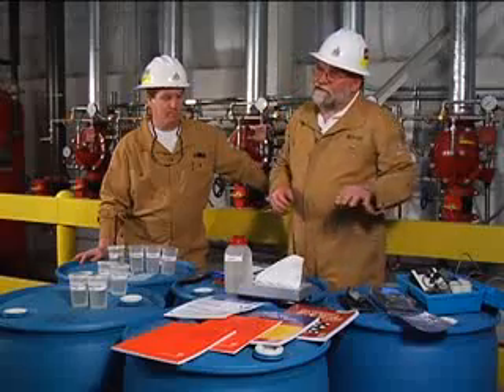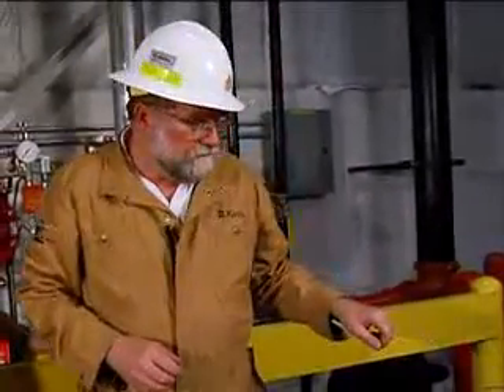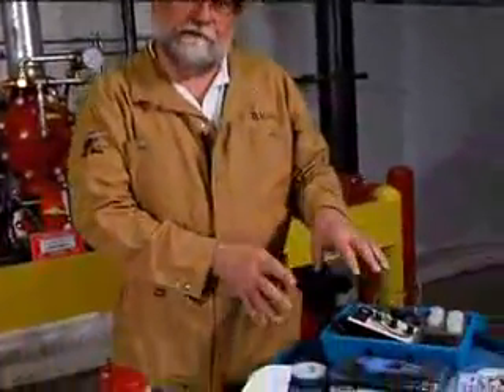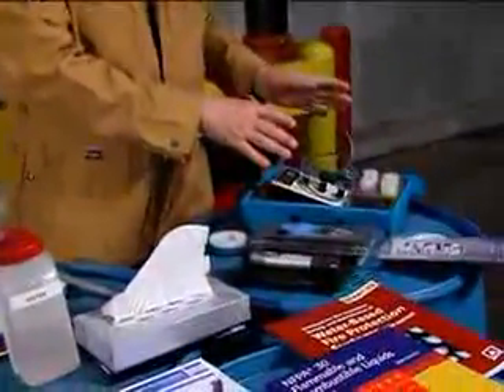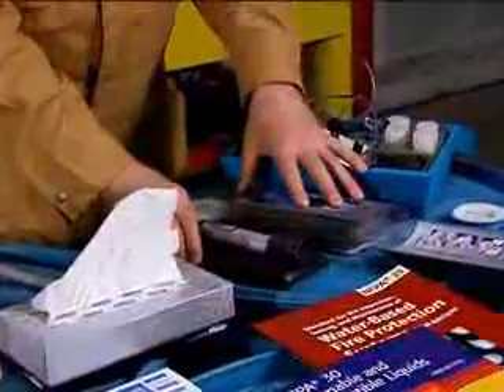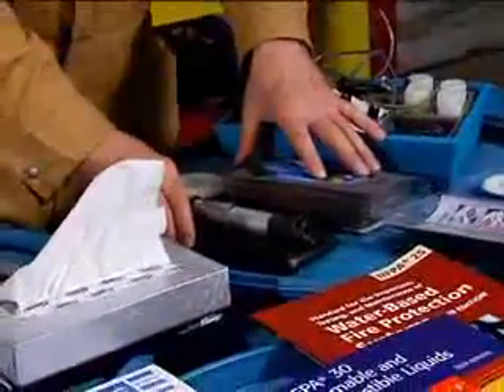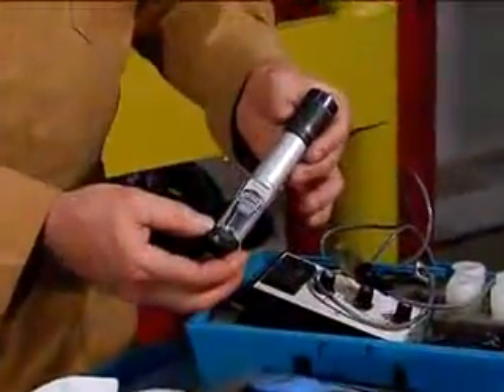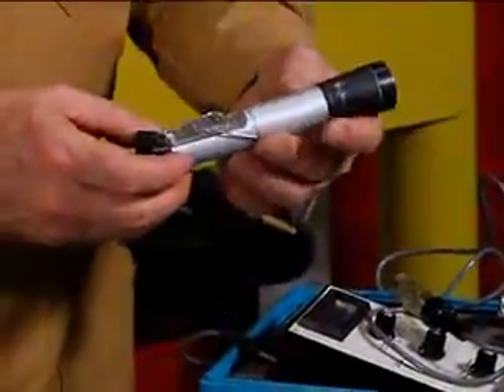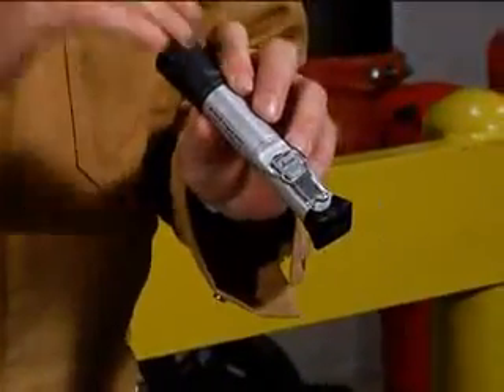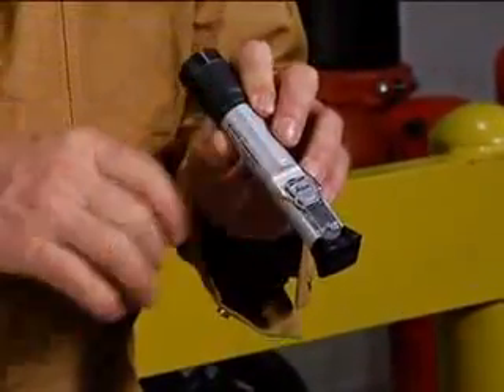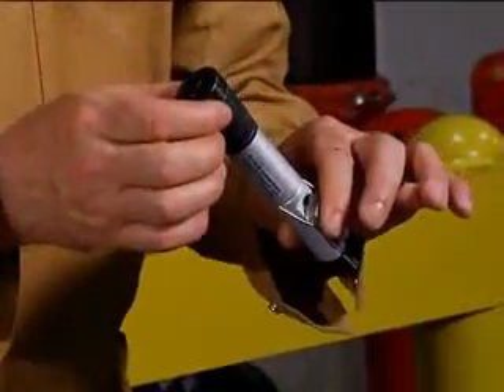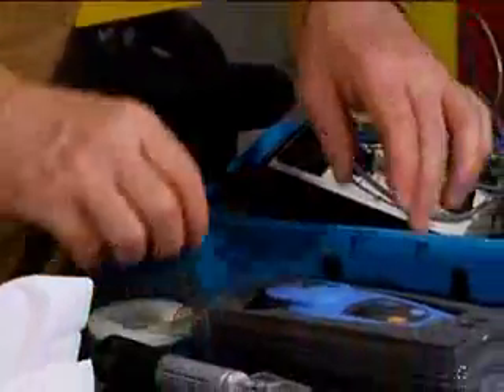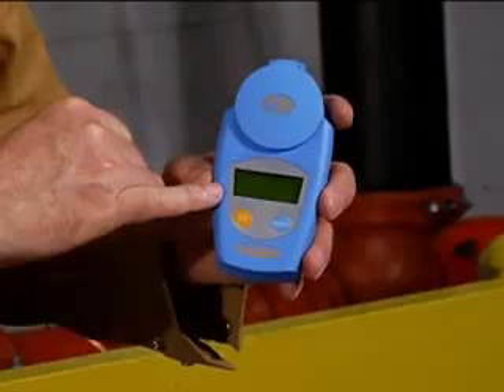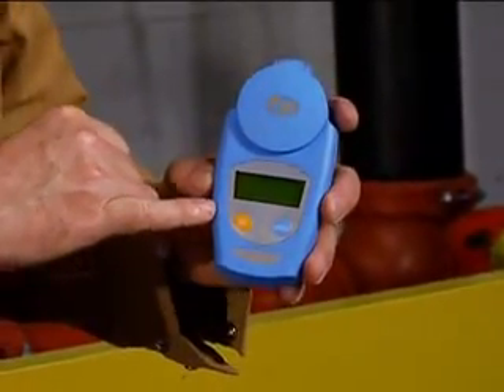We're going to go over with you the types of instruments that we can use in doing the test. Basically, it's either using the refractive index method or conductivity. We have two types of instruments here, which are refractive index meters. The first one is an optical device, which you read a scale. The light is bent as it passes through the prism, and you take a reading on the scale, looking through it similar to looking through a telescope. The second instrument is also a refractometer, but it gives you a digital readout. So it's very easy to use, it's user-friendly.